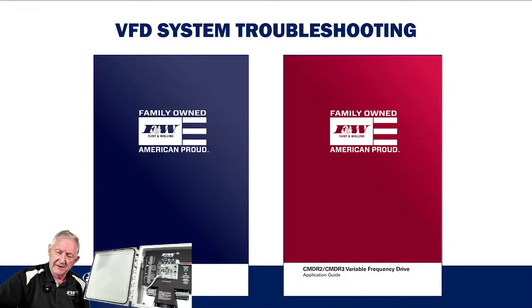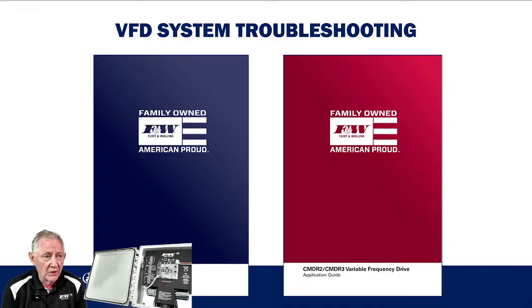Let me say this much. Don't just stop on the notion that you can provide constant pressure. There are other things out there that can do that that don't have anywhere near the features of a drive. When you talk about a variable frequency drive, here's why a customer would want one. One, they can have consistent pressure irrespective of the amount of water they're using. It's kind of like cruise control in a car. And the second reason why a customer would want to have a drive is because of the onboard protection. This drive is going to keep that pump from self-destructing if it gets into a situation like a deadhead or a dry run or anything else that may destroy that pump. With a variable frequency drive, you do have that onboard protection.